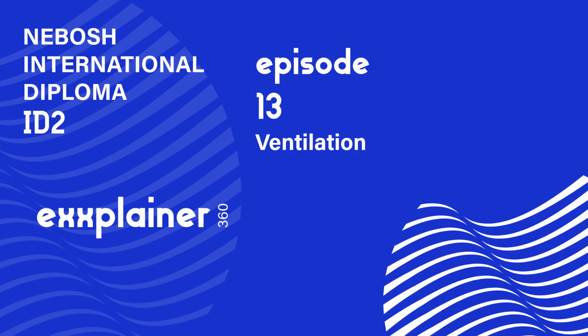Okay. But for high energy stuff, grinding, abrasive blasting, you might need 2.5 meters per second, maybe even over 10 meters per second capture velocity. Wow, that's fast. That's like fighting a dust storm. It really is. And those very fast-moving clouds are incredibly hard to control with just a simple capturing hood. Often you need to add partial enclosures, barriers, just to try and slow the cloud down first before the hood can grab it.